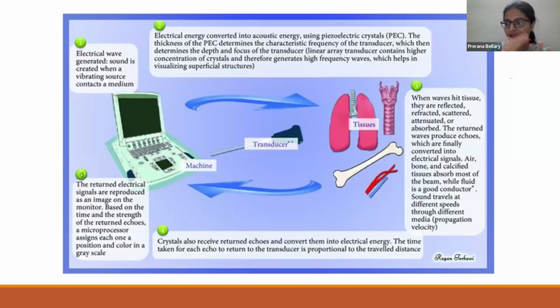So what we've spoken about until now is that an electrical wave is generated and a sound is created when a vibrating source contacts a medium. Next, electrical energy gets converted into acoustic energy using the piezoelectric crystals. The thickness of the crystal will determine the characteristic frequency of the transducer. That frequency is further going to tell us how deep it can focus, how clear the image is going to be, and so on. Then it goes and hits the tissues.